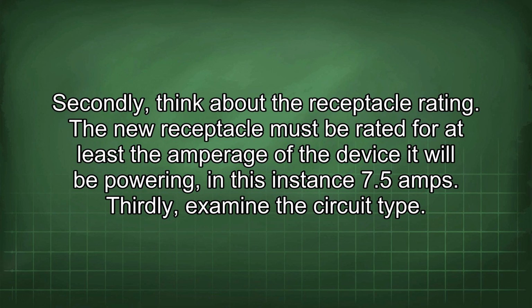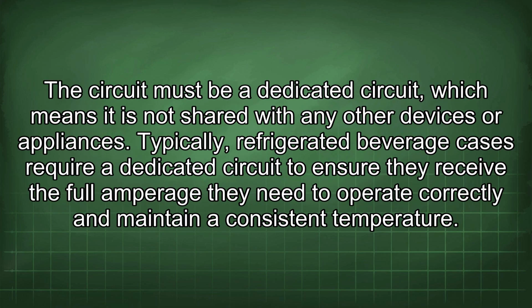The new receptacle must be rated for at least the amperage of the device it will be powering, in this instance 7.5 amps. Thirdly, examine the circuit type. The circuit must be a dedicated circuit, which means it is not shared with any other devices or appliances. Typically, refrigerated beverage cases require a dedicated circuit to ensure they receive the full amperage they need to operate correctly and maintain a consistent temperature.